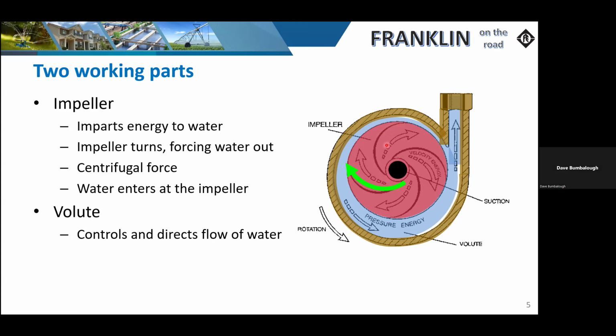And in most cases, these types of pumps are not very efficient. As a manufacturer, we try our due diligence to improve the performance and keep from recirculating. And what recirculation means is, as that water molecule is removed and starts flowing out of the volute, sometimes it will try to recirculate back through this section right here to get back to the eye of the impeller. And so tolerances have been tightened up on that, along with some sealing methods, to ensure that doesn't happen.